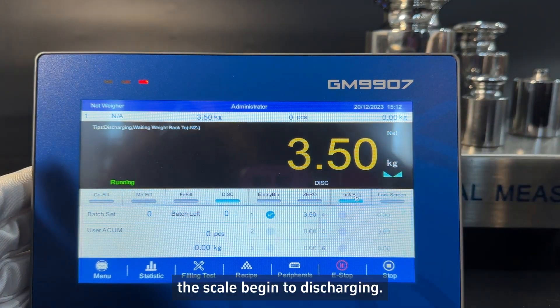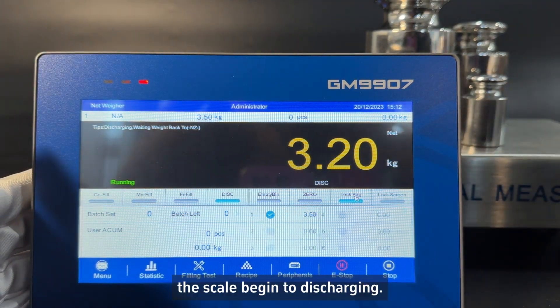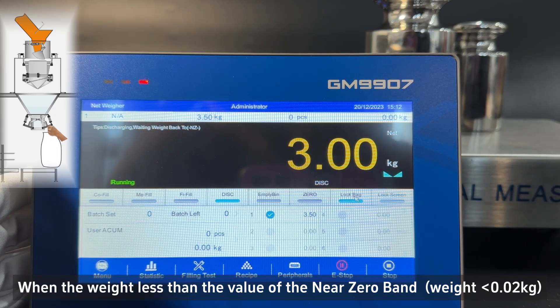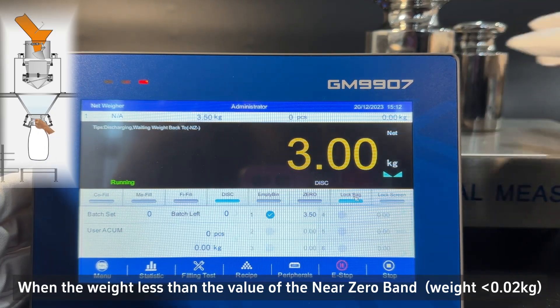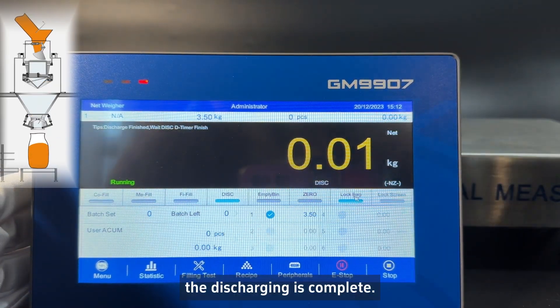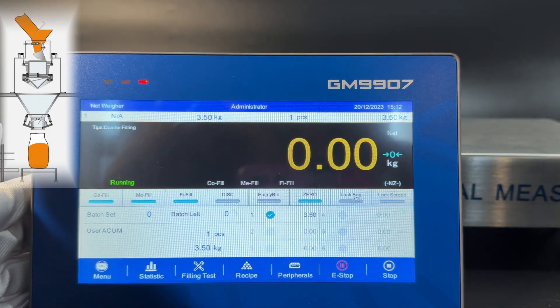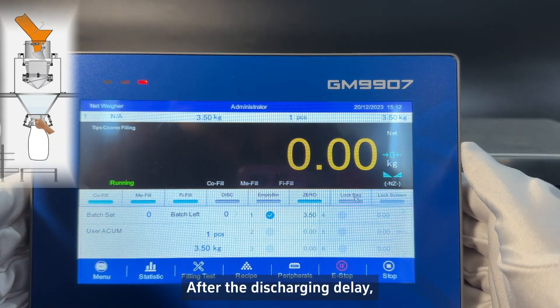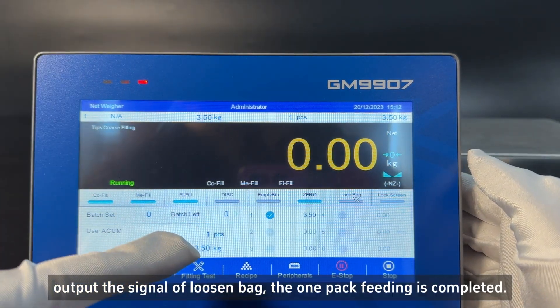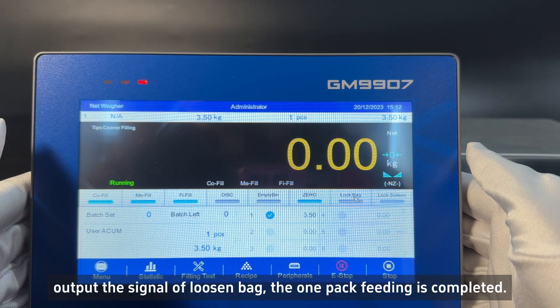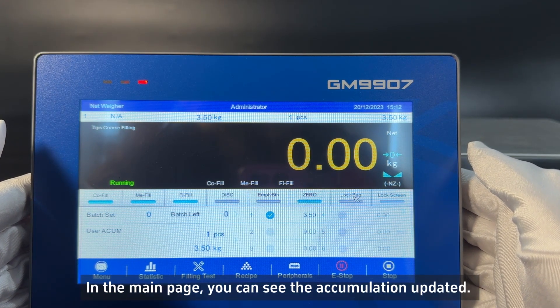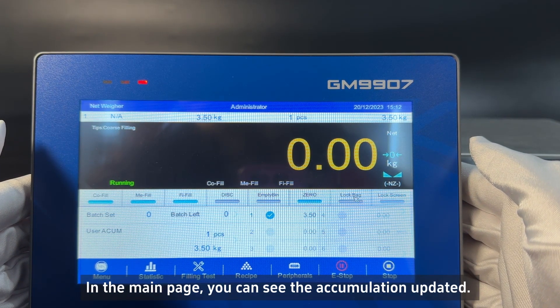The scale begins discharging. When the weight is less than the value of the near zero band, the discharging is complete. After the discharging delay, the signal of loosen bag is output. The one-pack feeding is completed. In the main page, you can see the accumulation updated.